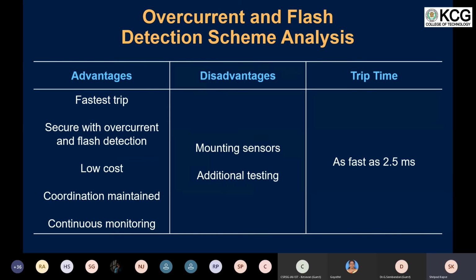Some of the disadvantages, or maybe some of the additional effort that would be involved in this particular scheme, would be to mount these sensors and some additional testing activities. But on the other hand, the customers are going to get the added advantage of low cost, and this protection operates by maintaining the existing coordinated system, and you are also eliminating any sort of cyber threats because we are not going to connect the system to any of the communication equipment.